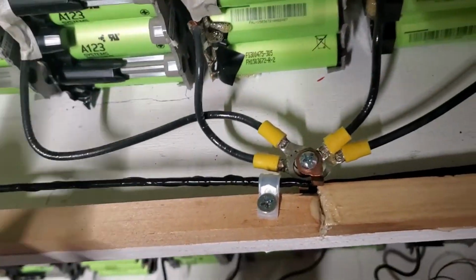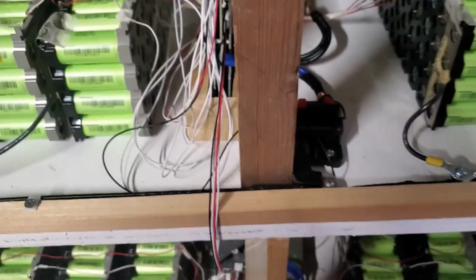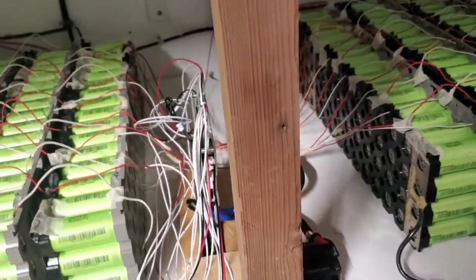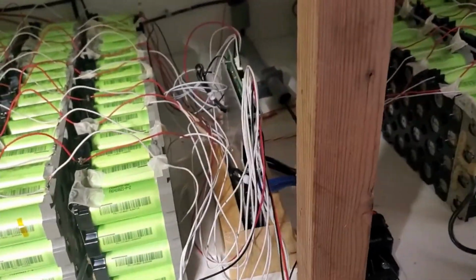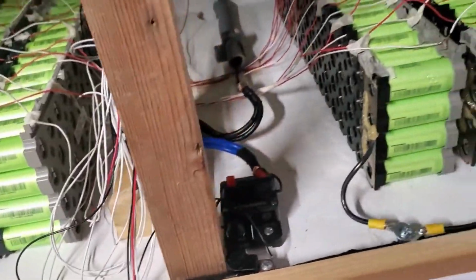If you go beyond 100 amp, you're gonna have a problem. Now the wires going up to the inverters, they double. You see, it's in there, it's two bus bars. Now I'm assuming two. If one can produce 100 amp, two can produce 200 amp. That's why behind the inverter I don't have the breaker yet.